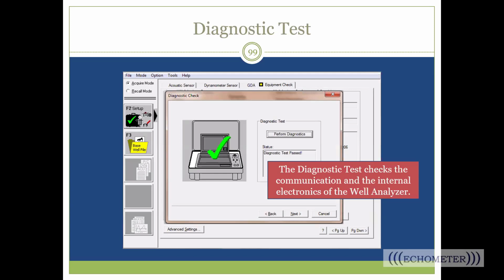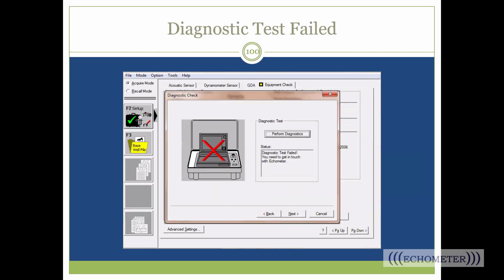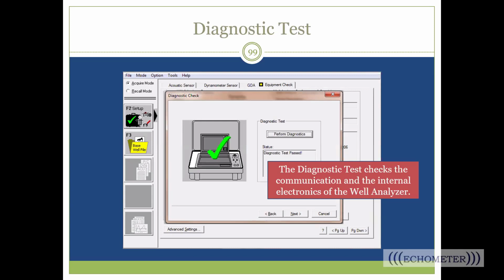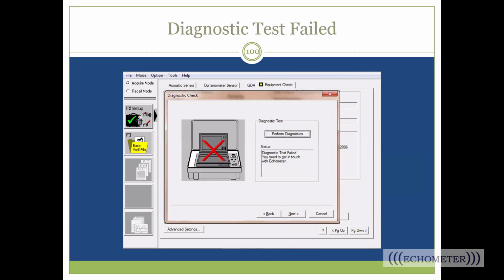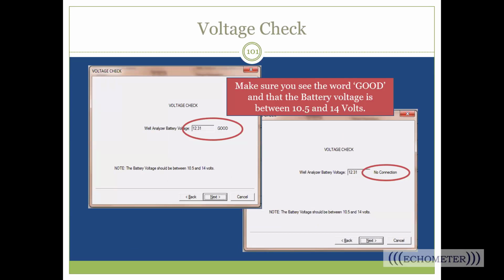Click next. The software will do a diagnostic check of the processor, sort of the internals in the well analyzer. If everything's okay, you'll see this nice big green check mark. If there's a problem, you'll see a red X, and it will say you need to get in touch with Echometer. Our technician who works on the well analyzers, Jeff, can help give you some troubleshooting tips and talk you through it if you're having a problem with your well analyzer.